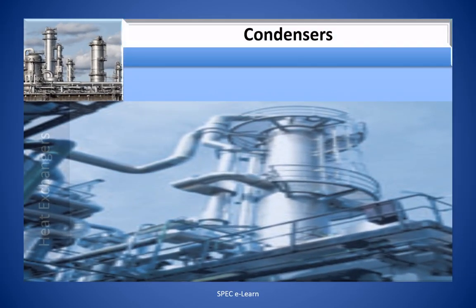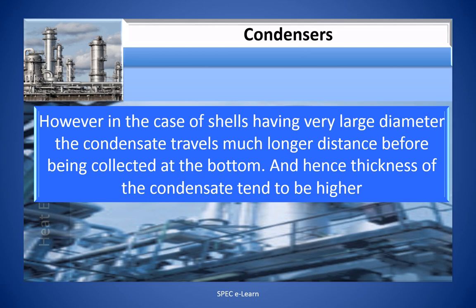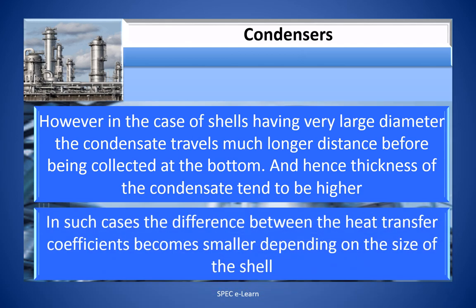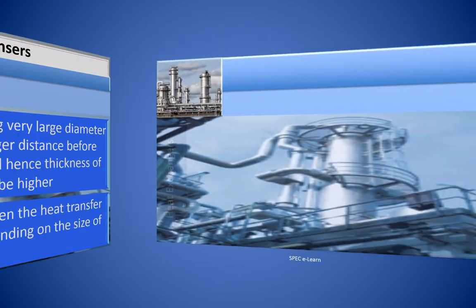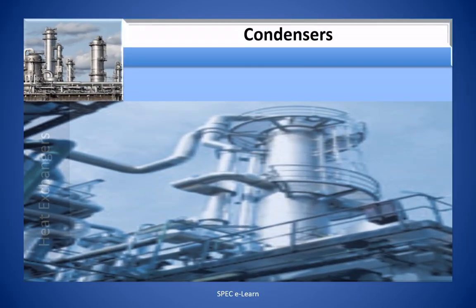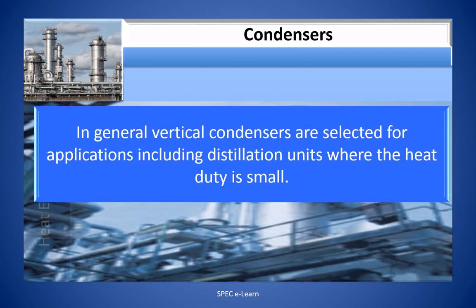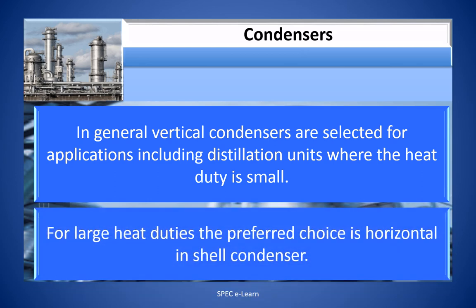However, in the case of shells with very large diameters, the condensate travels a much longer distance before being collected at the bottom, and the condensate film thickness tends to be higher — so the difference between heat transfer coefficients becomes smaller depending on the shell size. In general, vertical condensers are selected for applications including distillation units where the heat duty is small, while for large heat duties the preferred choice is horizontal in-shell condensers.